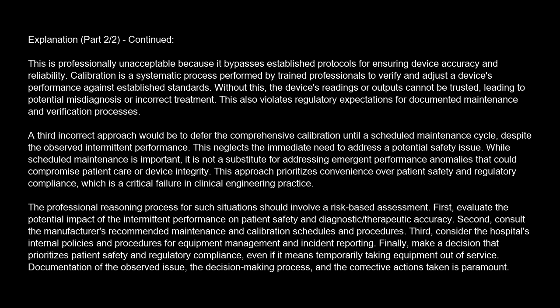First, evaluate the potential impact of the intermittent performance on patient safety and diagnostic/therapeutic accuracy. Second, consult the manufacturer's recommended maintenance and calibration schedules and procedures. Third, consider the hospital's internal policies and procedures for equipment management and incident reporting. Finally, make a decision that prioritizes patient safety and regulatory compliance, even if it means temporarily taking equipment out of service. Documentation of the observed issue, the decision-making process, and the corrective actions taken is paramount.